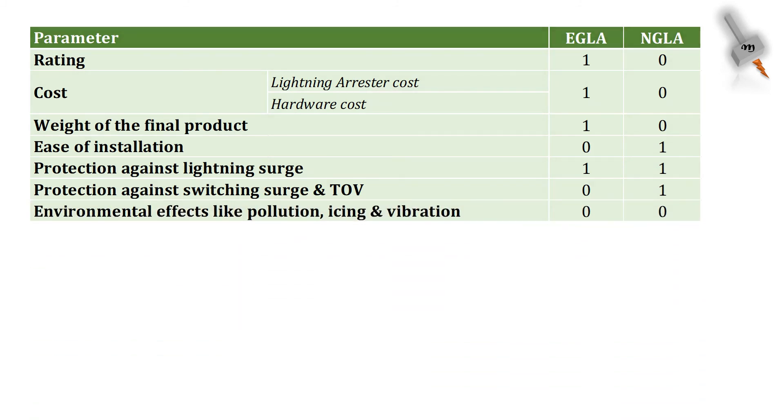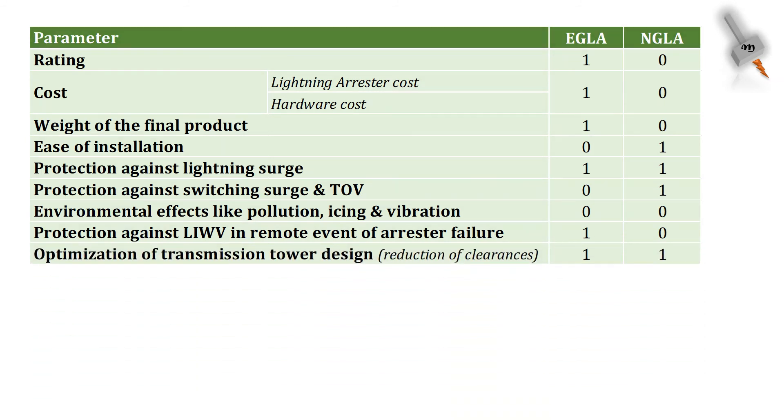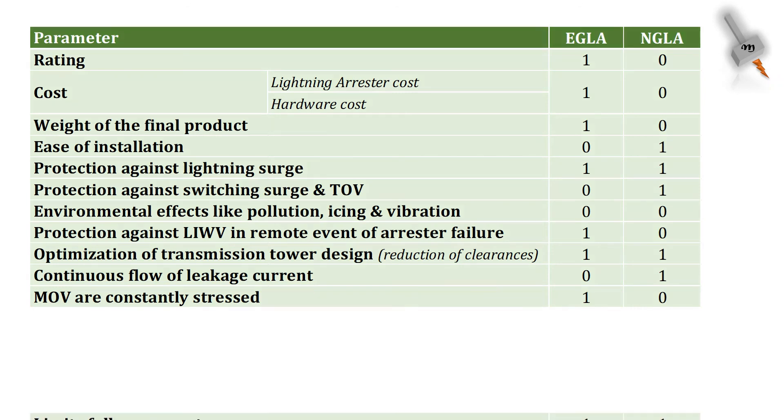Environmental factors like pollution, icing and vibration has the same level of detrimental impact on EGLA as well as NGLA. In case of end-of-life event, the insulation withstand protection of EGLA has better performance over NGLA. For optimization of transmission tower design and reduction of clearances, both EGLA and NGLA have the advantage. Leakage current is surely a disadvantage for NGLA and here EGLA has the advantage. Since NGLA is electrically constantly connected in the circuit, its zinc oxide blocks are constantly stressed. Limiting follow-on current is achieved perfectly by both EGLA and NGLA. Finally, it is easy to locate a failed NGLA as against to EGLA.